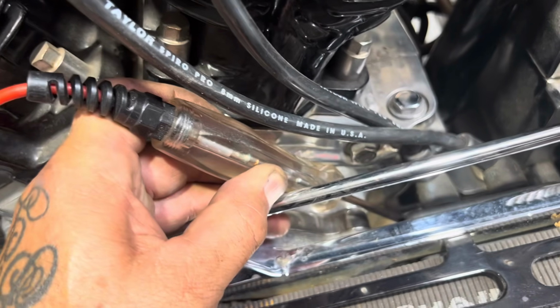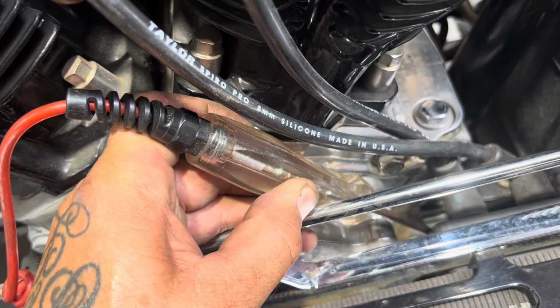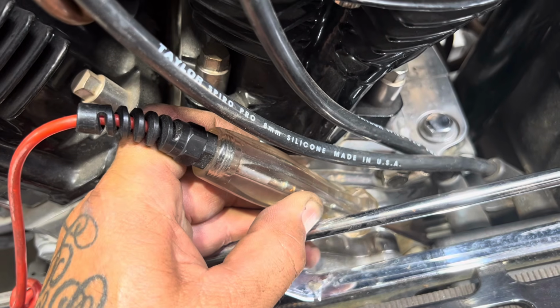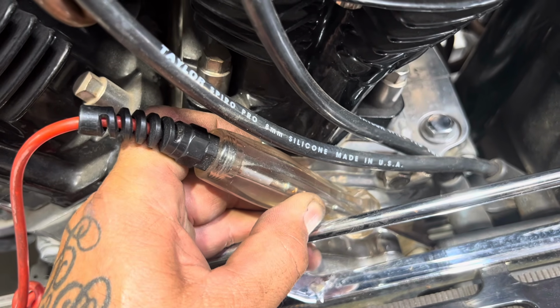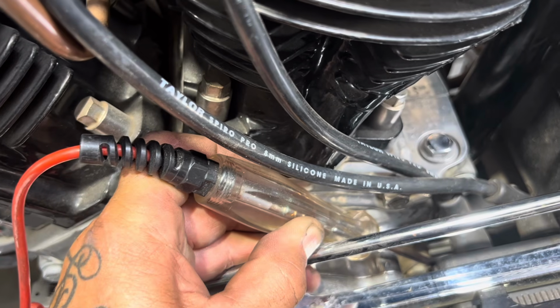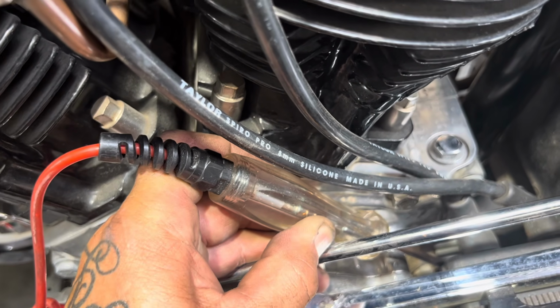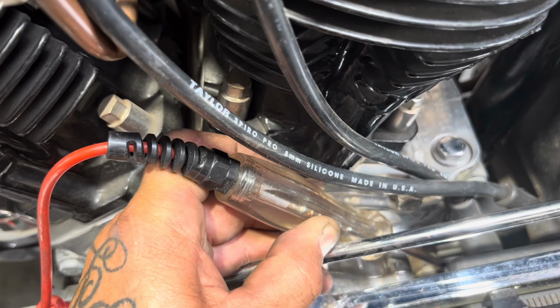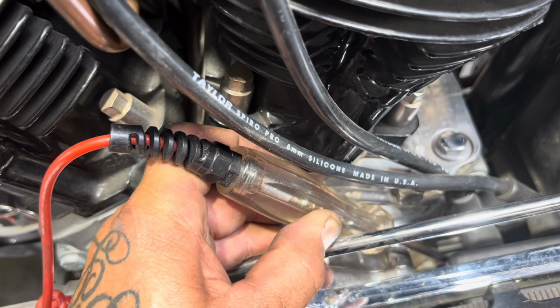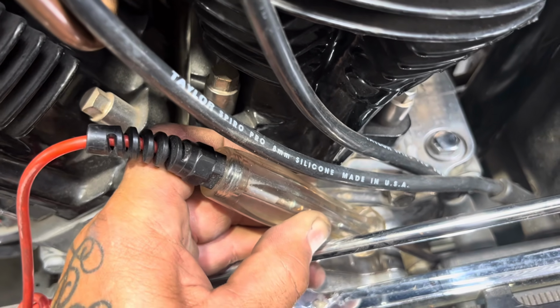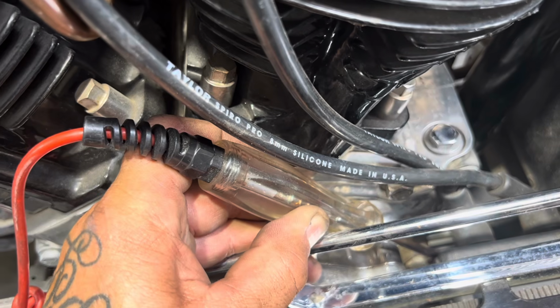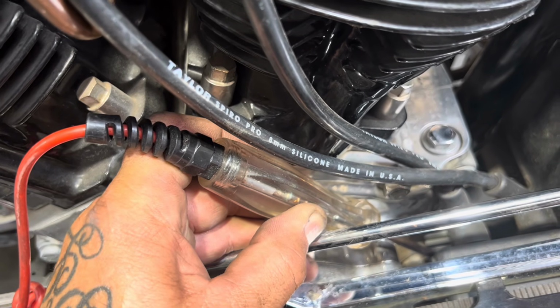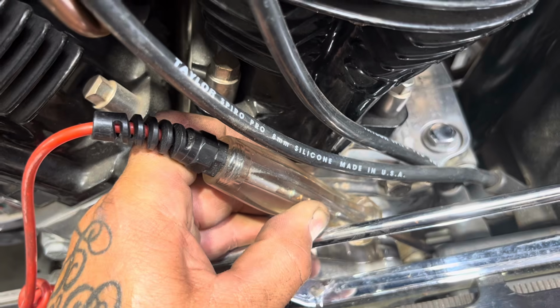What I'm going to do now to troubleshoot my problem is I'm going to jump power from the circuit breaker right directly to the coil. I'm going to bypass the wire that's in the circuit. Then I'm going to go check the circuit breaker and see if those points are arcing. If they do arc, that tells me there's something wrong in this wire. Maybe the wire is broken or it's grounded somewhere. If not, then the coil is probably bad.